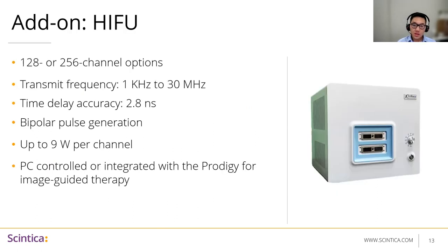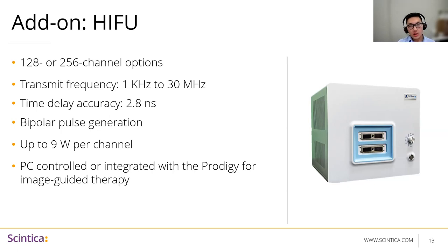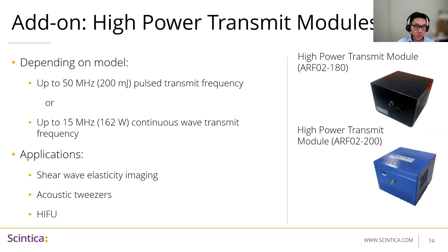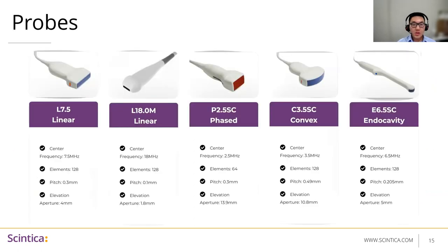The HIFU add-on unit can be used either by itself with any PC you provide, or incorporated with the Prodigy using the software interface to synchronize them together. It has a similar transmit frequency range of 1 kilohertz to 30 megahertz, 2.8 nanosecond time delay accuracy, bipolar pulse generation, and provides up to 9 watts per channel — and this can go higher for pulse applications. The two high-power transmit modules can be used for shear wave elasticity imaging, acoustic tweezers, and HIFU, providing up to 50 megahertz pulsed transmit at 200 millijoules per pulse, or 15 megahertz in continuous wave at 162 watts.